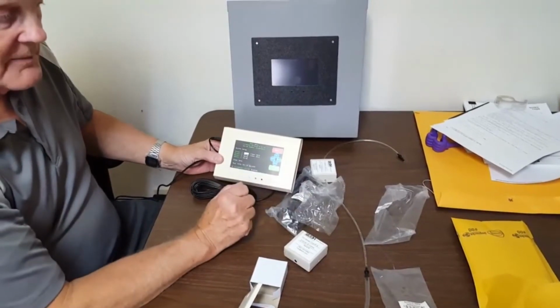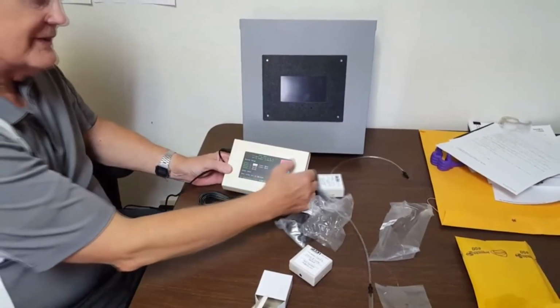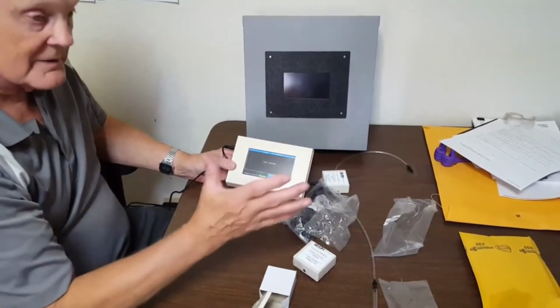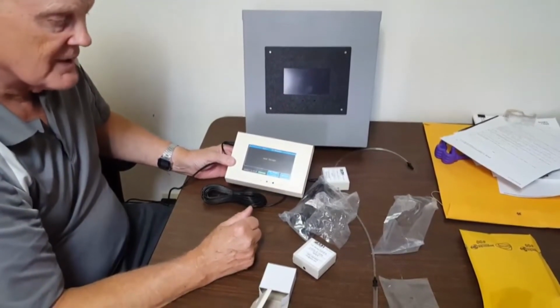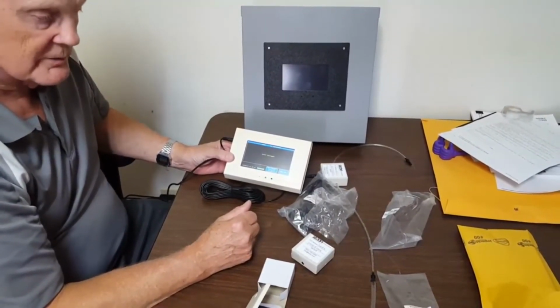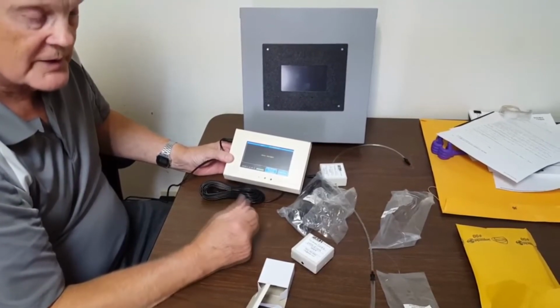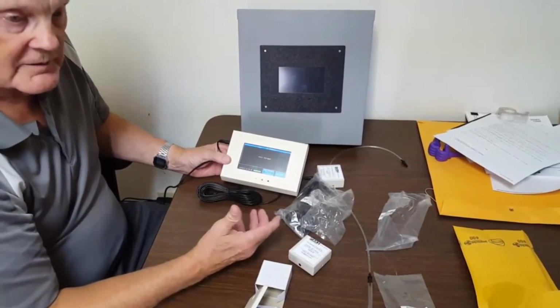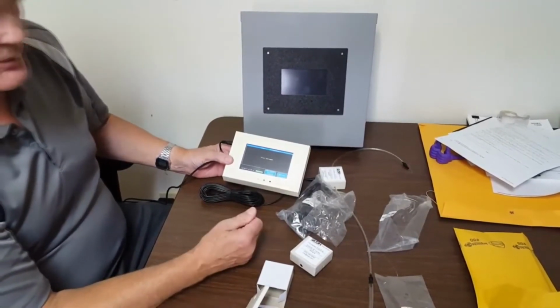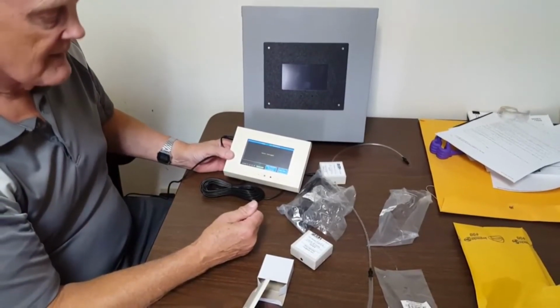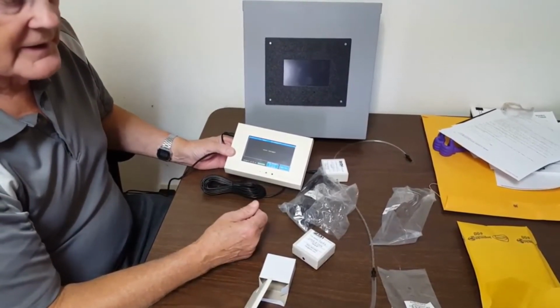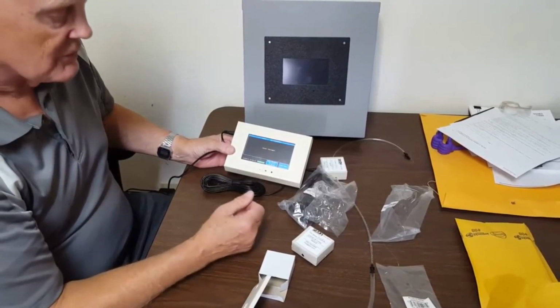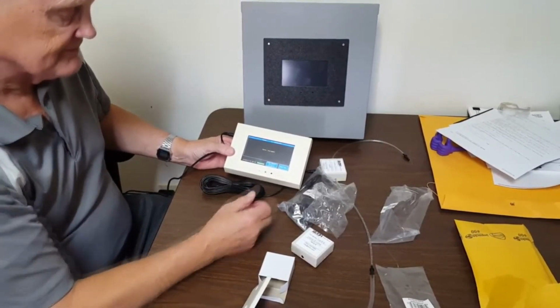When you do this, make sure the pressure between the two rooms is the same, that you haven't already pressurized one of those rooms. Once you've zeroed out the sensor, you can create pressure in the room you want to be positive or negative, and that will give you a reading of the differential pressure.